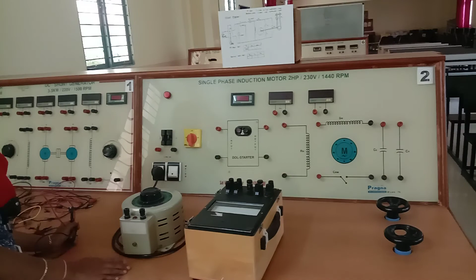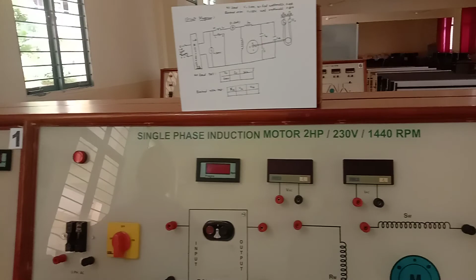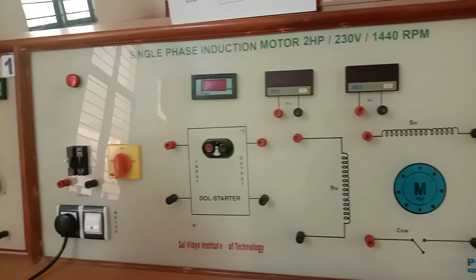So this is where we are going to conduct the suitable test on a single phase induction motor, where it is of 2 HP, 230 volt, 1440 RPM, and here we are going to make use of this arrangement, that is capacitor start, capacitor run, and as well we are making use of this auto transformer and the watt meters.